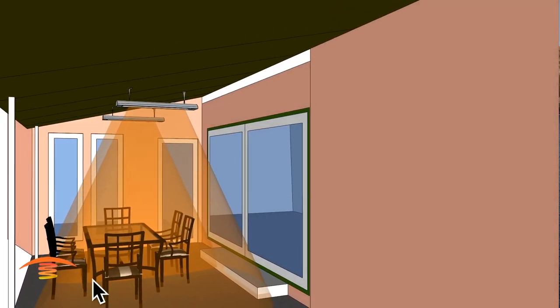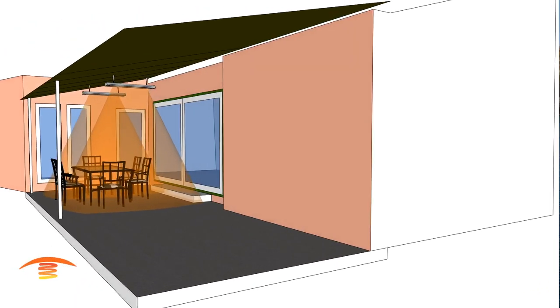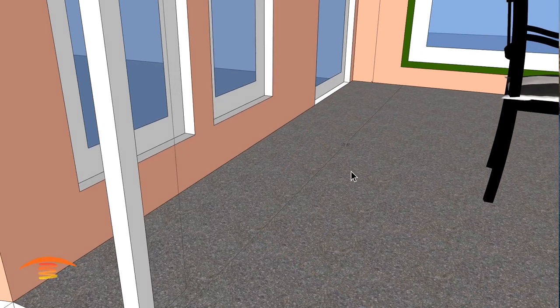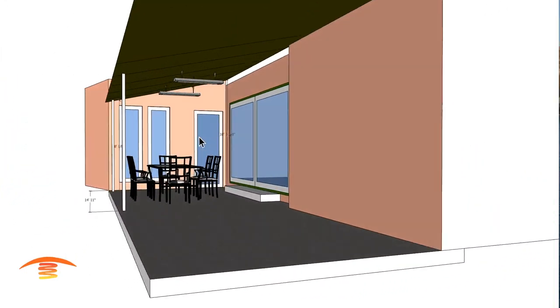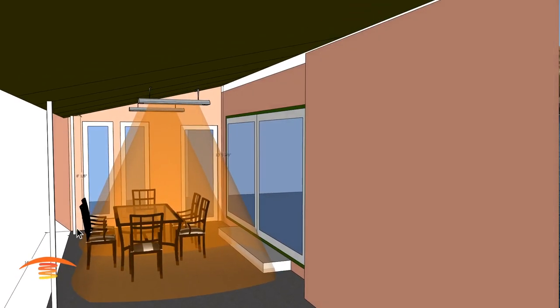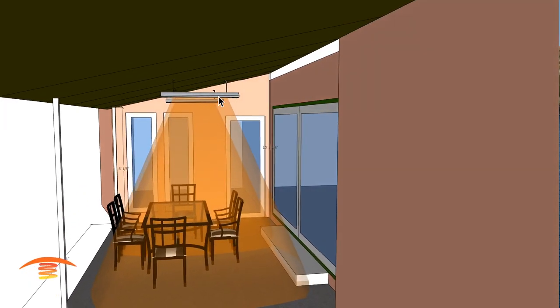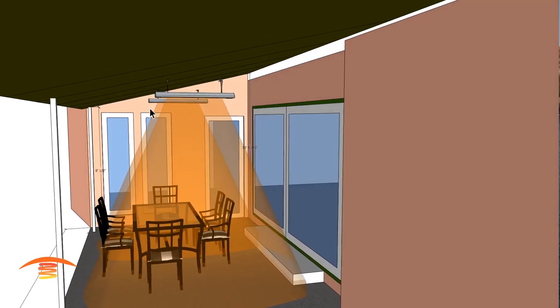We're capturing most of this area and I have it centered based on the roughly ten feet eight inch span. The heater is centered in that location, and when you throw that heat ray back on you can see that the outer chairs aren't as well heated as the inside area. You could move the heaters down a little bit.